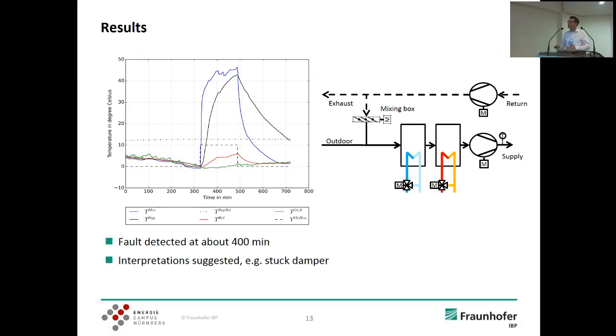And what you can see here is that we analyzed data for one year, for one air handling unit, where we deploy the 28 rules in the APAR rule set, and we detect the fault in this specific case. So this is the temperature, so we have here mixed air temperature, supply temperature, set point, and so forth. First of all, we detect one fault here. But the second problem is to actually isolate the fault and determine its root cause. The interpretation suggested by the APAR rule set is that this is caused by some stuck damper.